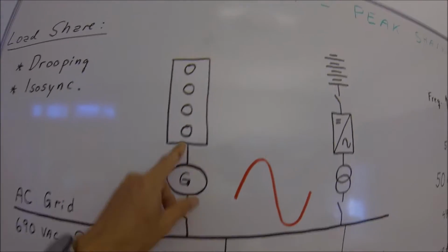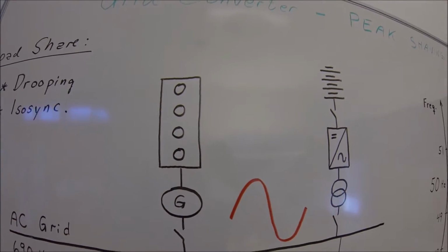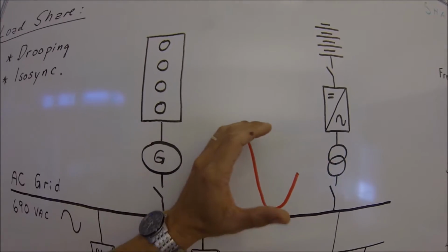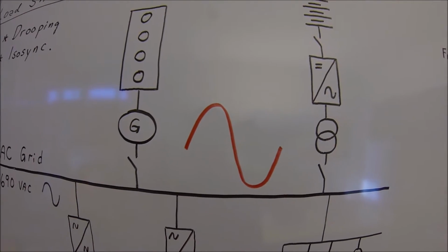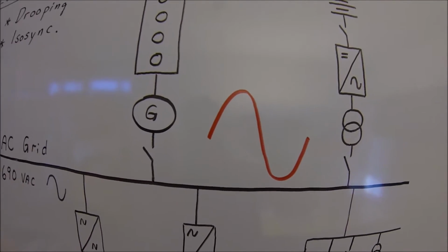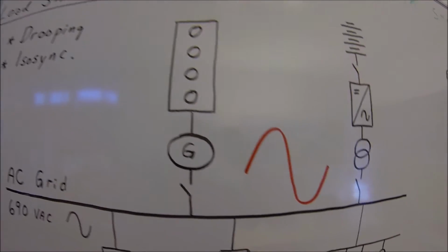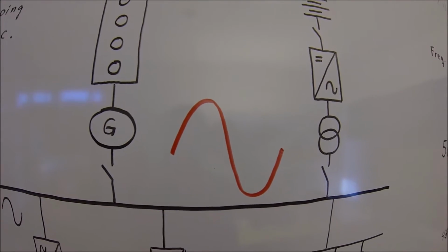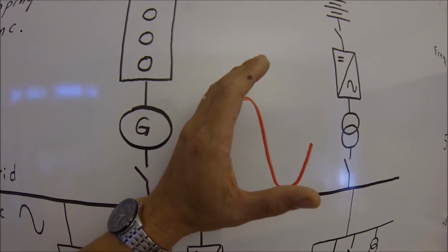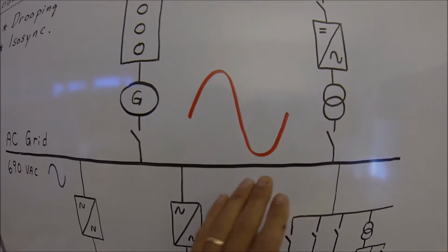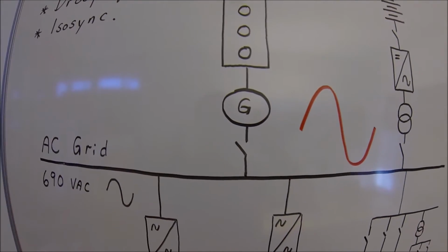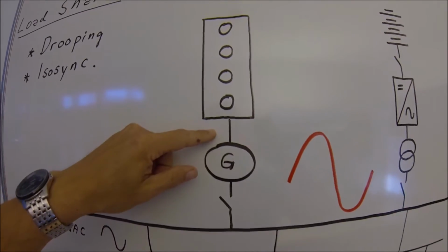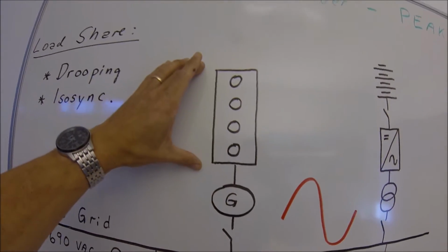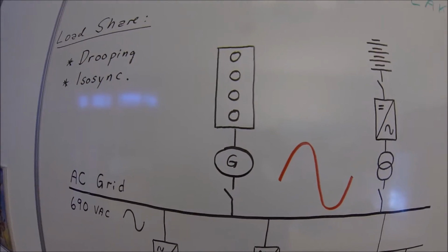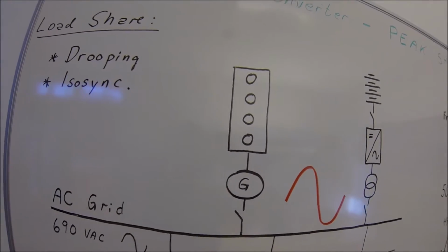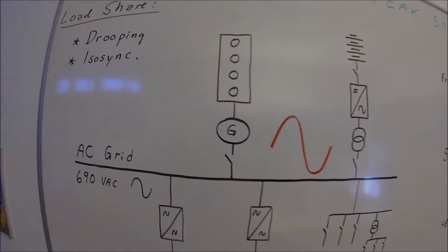Active load, that is load mechanically on the diesel engine, is pushing on the ship frequency. Let's say the ship frequency is 50 hertz. If this diesel generator tried to create 50.5 hertz, it means that you are pushing on the frequency and there will be an active current going on this diesel engine, and it will be seen as a mechanical load on the diesel engine. You actually can hear it, you can see it on the exhaust smoke from the diesel that it actually is loaded.